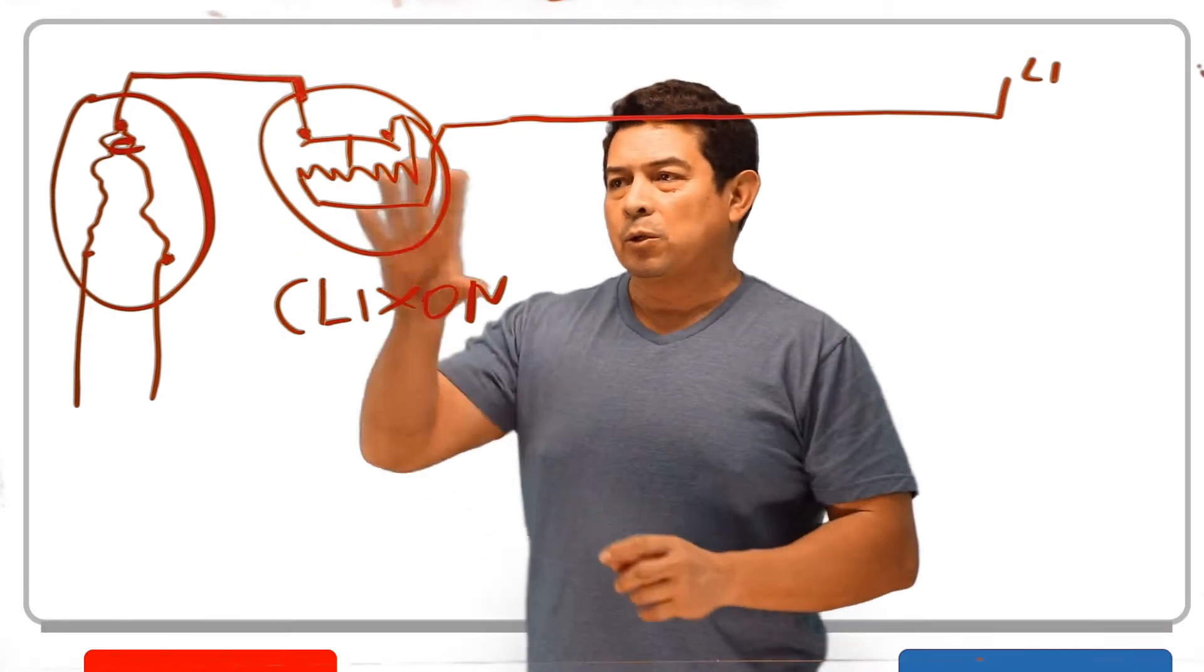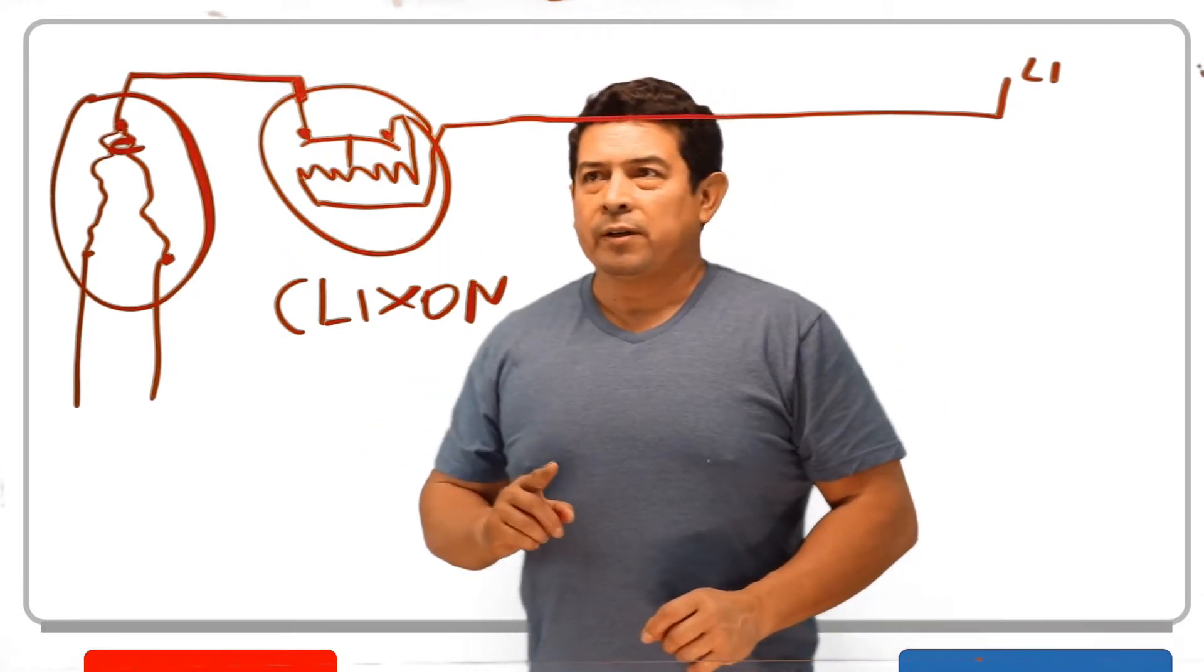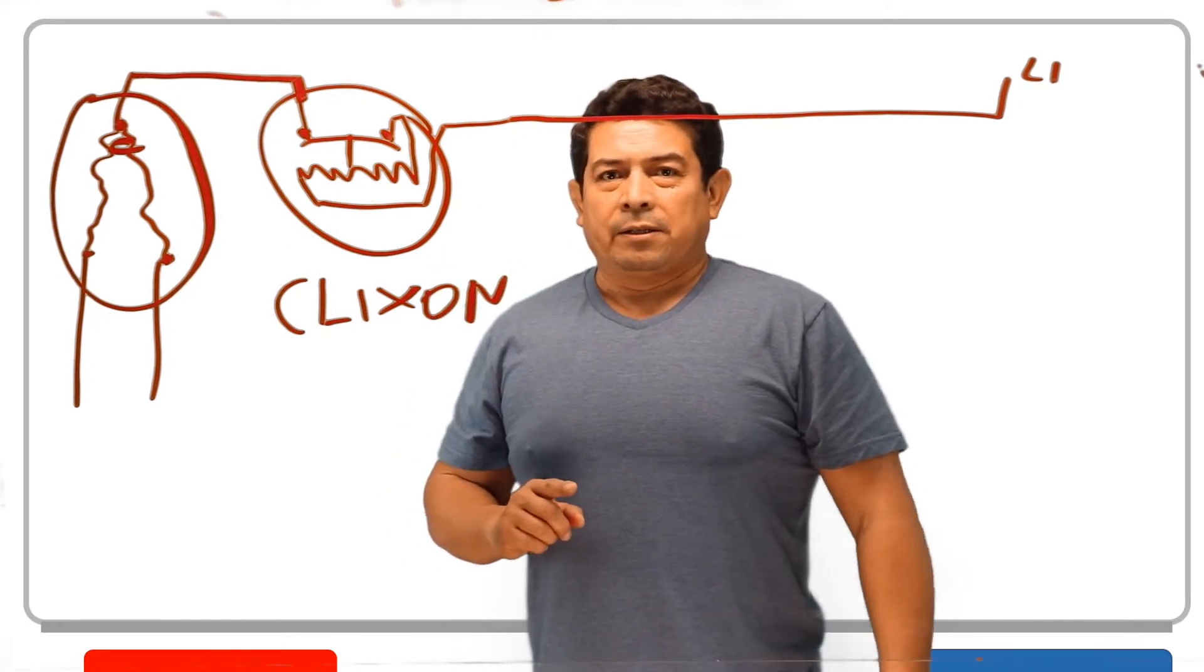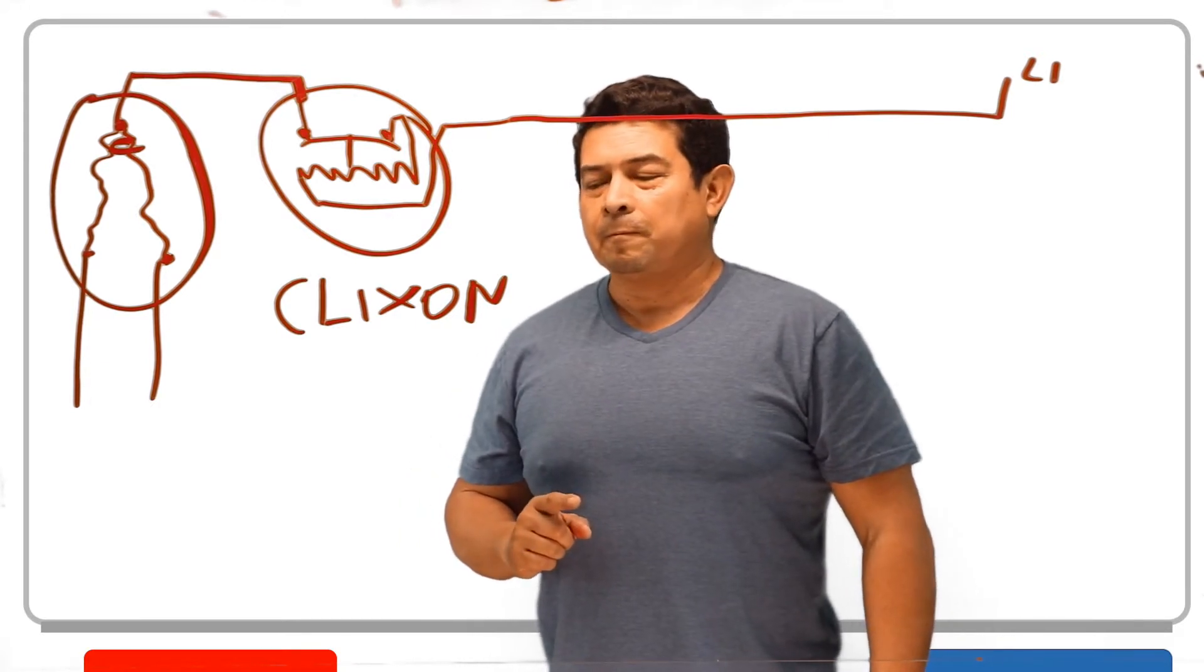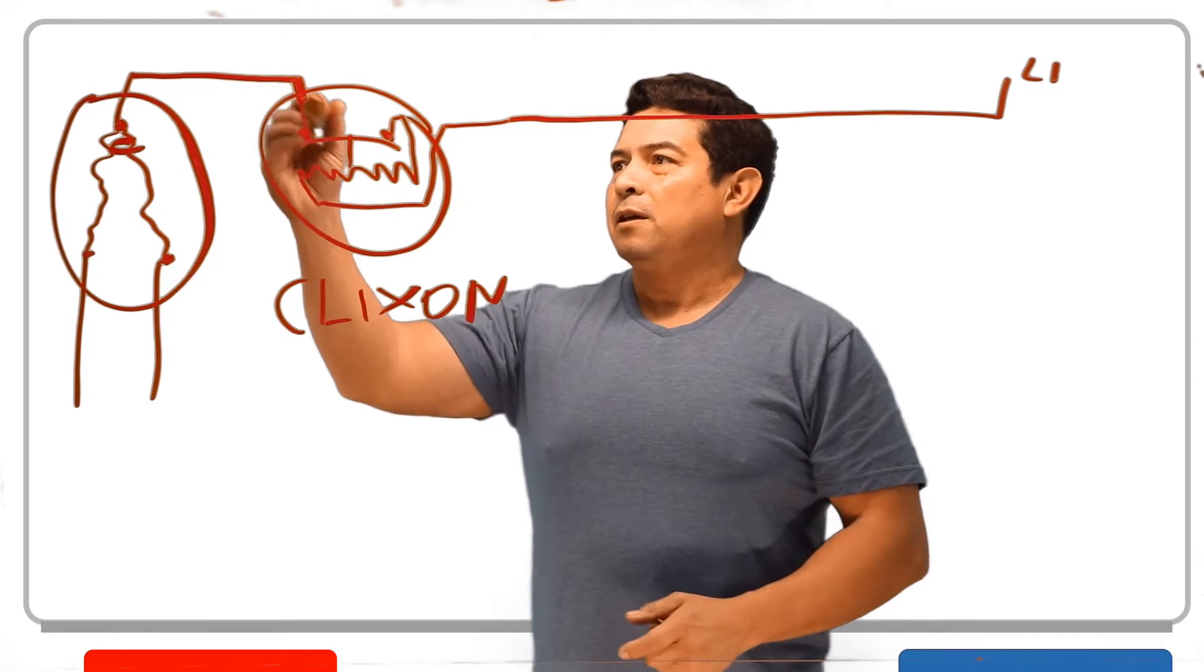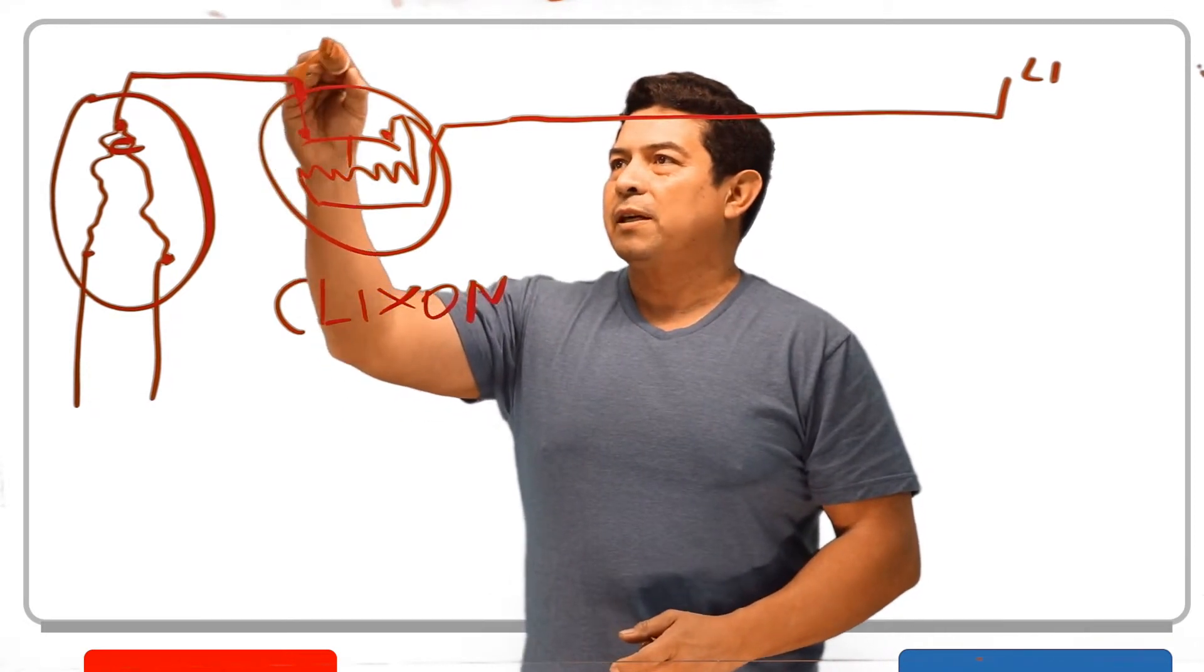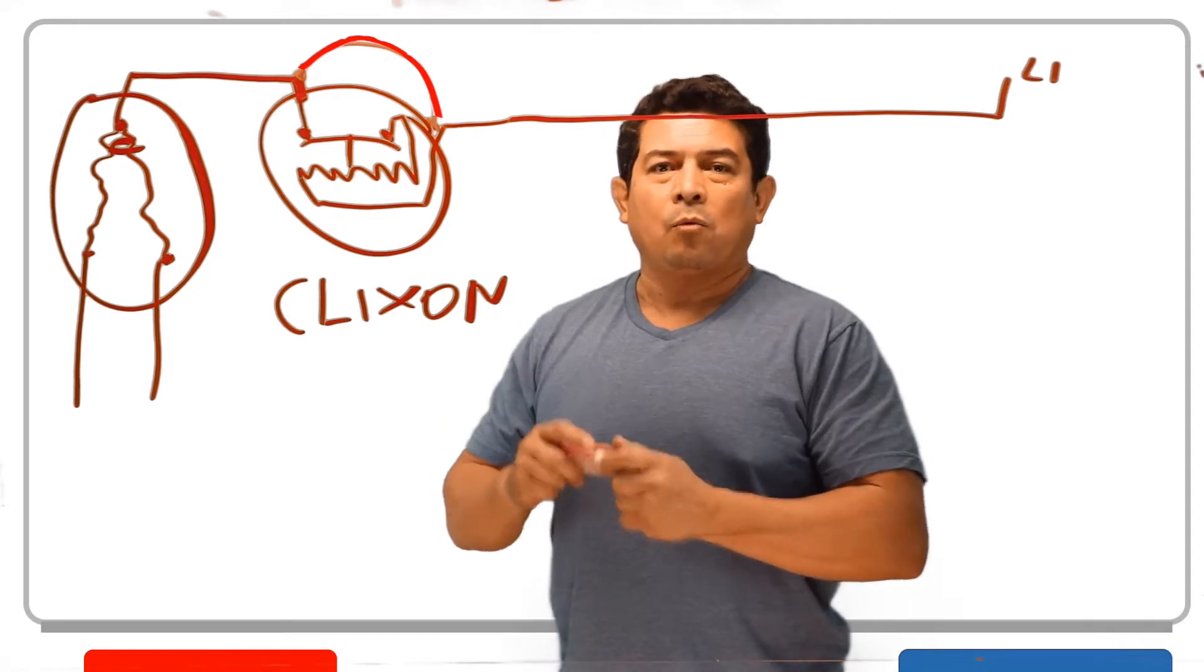So keep this in mind for your Clixon. All it is, like I said, it's an overload. Another thing I wanted to point out is can you bypass this? Well, of course you can, but should you bypass it? Now, one thing that I have done in the past is I have taken and just hooked up a wire from this side over to this other side. Why?